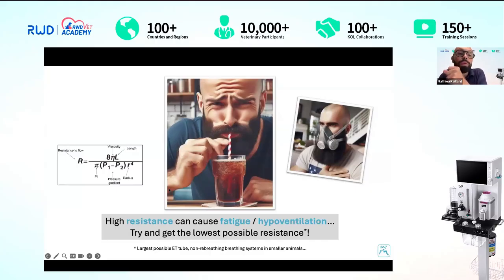If I reduce the radius by about half, so if I reduce the radius of my pipe by 2, you see from that formula, you don't need to remember that formula by heart, but just be aware that if you reduce the radius by 50% in your airway, you increase the resistance by 16, because in the formula of the resistance, the radius is at the fourth. And that is not without any consequence, because high resistance will cause fatigue and will cause hypoventilation. So when we induce anesthesia, we need to be very mindful about the size of our ET tube. That should be a compromise between not damaging the airway, but being as wide as possible to limit the impact of our ET tube on the resistance.